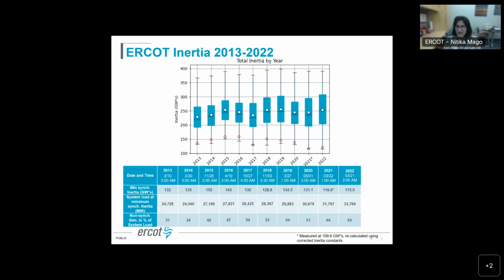Here's an outlook of our inertia, to share our spread in inertia. Even though we've added a whole bunch of wind and solar, you'll notice that our inertia has not declined at a significantly fast rate as our renewable fleet has increased. The lowest inertia we've operated at is about 115 gigawatt-seconds, from March last year. Through our studies, we've established a critical inertia, the level below which we do not plan to operate, at around 100 gigawatt-seconds. So we are still far away from operating in what we'd consider the danger zone from an inertia perspective.